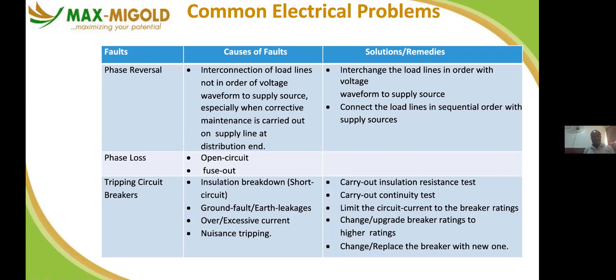So tripping circuit breaker, could be insulation breakdown, or short circuit, when live and neutral come together, or two cables come together. So it causes the circuit breaker to trip. Could be ground fault or earth leakage. So it could be anything, maybe a bird or a reptile died along your installation line and bridged the two cables together. It can lead to circuit breaker trip, most especially in a very tight distribution, where reptiles, like wall gecko and rat, can gain access. So you have to ensure that those appliances are well taken care of to prevent reptiles from breaching them.